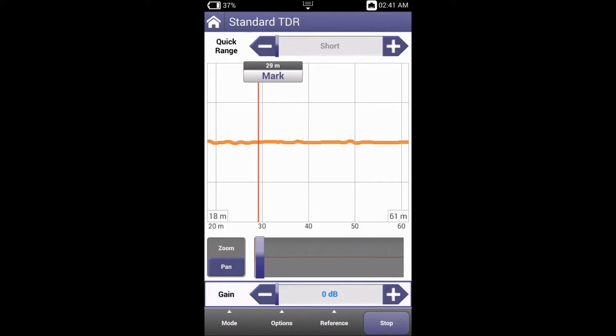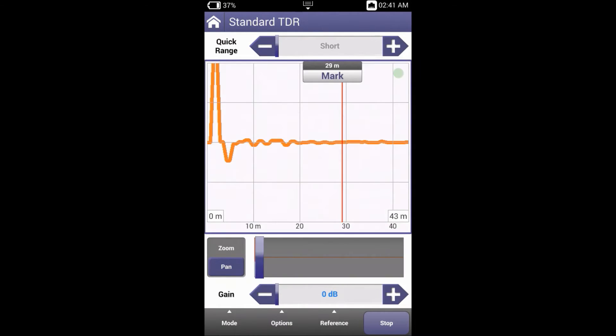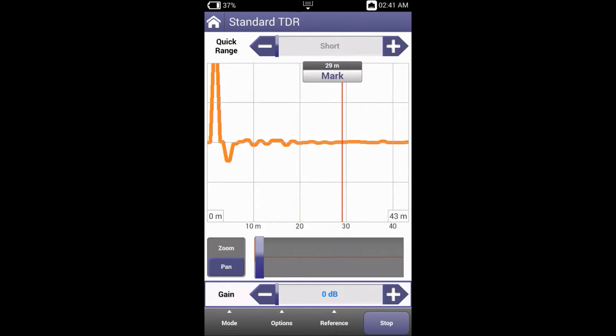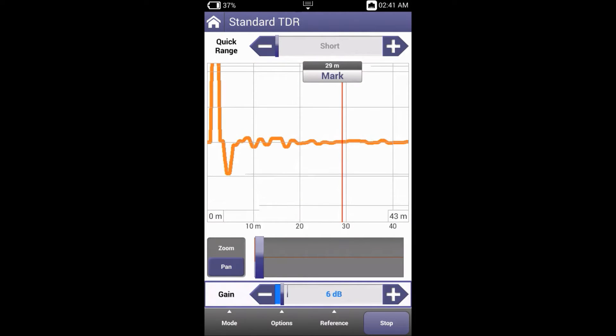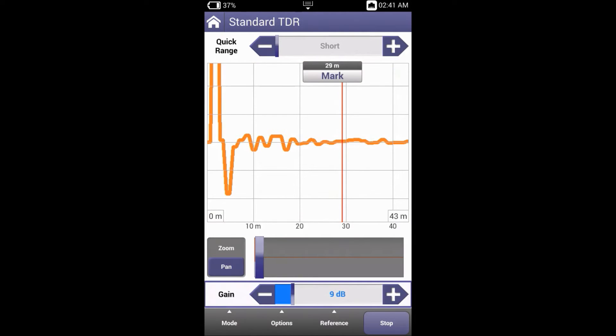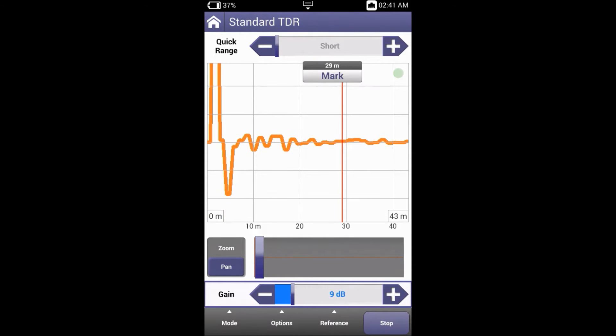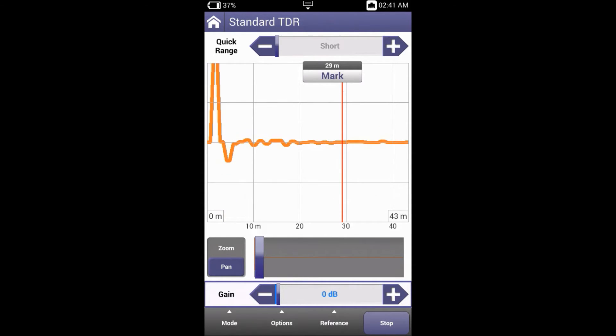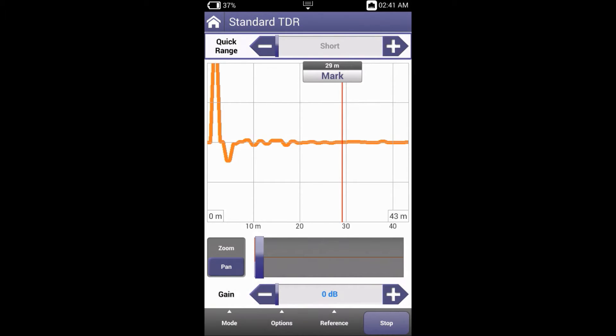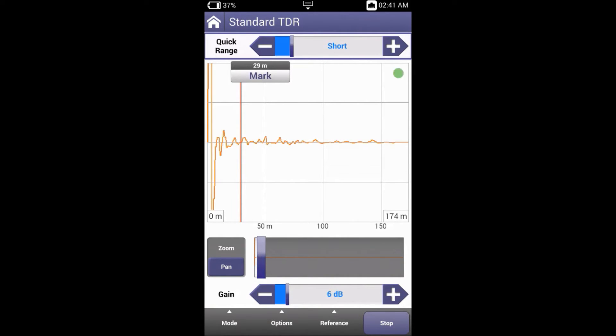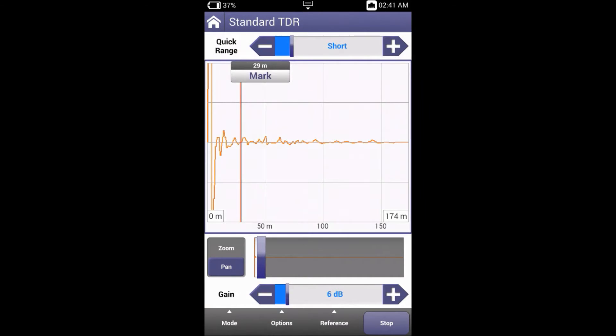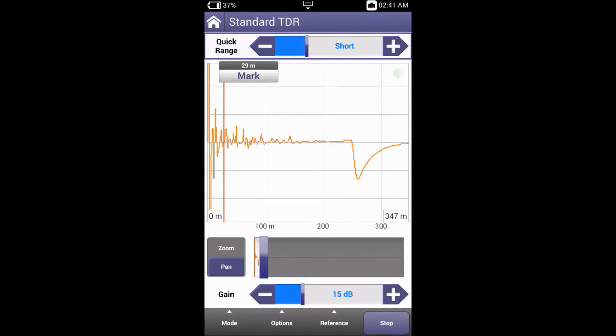Let's have a look at what this looks like. Always begin with your lowest gain setting and slowly step up. For example, I'll increase my quick range and see that there's a short on the line at about 250 meters. Now if I was to increase my gain, I'd see a lot of noise at the beginning.